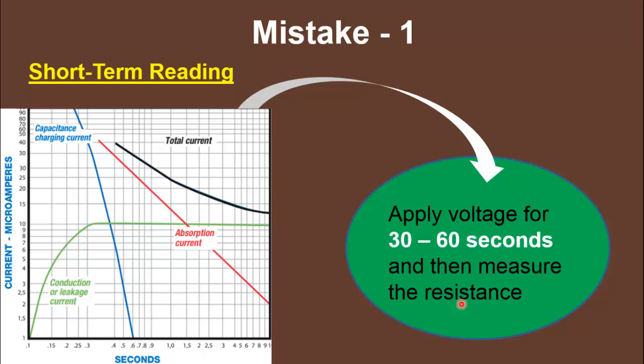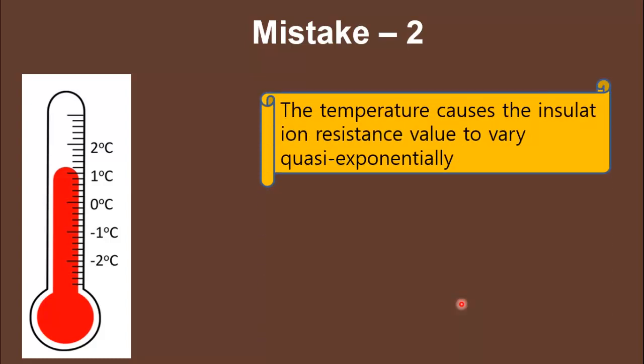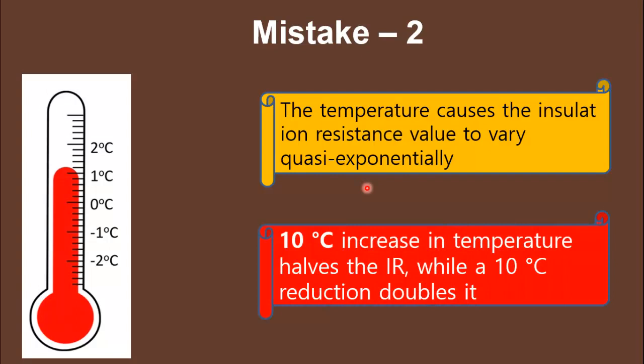That incorrect reading does not reflect the true insulation condition of the tested machine. The second — and most important and common — mistake is the effect of temperature while performing the Megger test. Temperature causes the insulation resistance value to vary quasi-exponentially. As a rough rule, a 10°C increase in temperature halves the insulation resistance measurement.